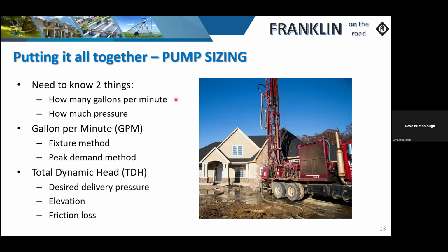A few questions will need to be asked, and in some cases, there are things that are out of the installing contractor's hands. I think it's vital that as an installing contractor you have a good relationship with the actual building contractor. And when he subcontracts out the plumbing inside the home, I think we need to educate on the size of the pipe, because a lot of times we run into friction issues. We're doing everything we can on the well side, but what often happens is that when we get to the application, the size of the pipe has been reduced and/or there are a lot of restrictions. We end up totaling up friction loss pretty high in that application.